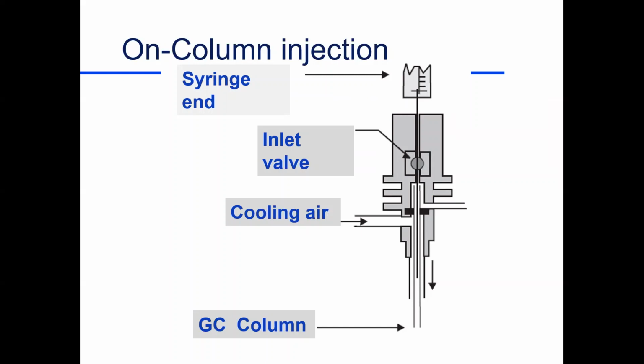So we've got a syringe here and a really long needle. In this case, you've got your carrier gas coming in here, that gets to your column and keeps everything going on here. But you've got a syringe with a long needle. You put it down here, it goes to this valve, goes down into the column, just for the gas chromatographic ovens. So it can be fairly cool down here. None of this is heated, but we've got compounds that thermally decompose. A long syringe, and you have a cold injection port, and you put your sample down here, and it goes on its merry way for separation.